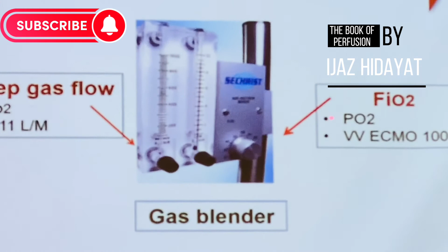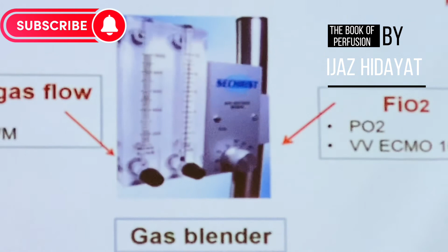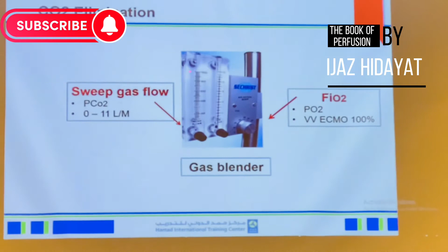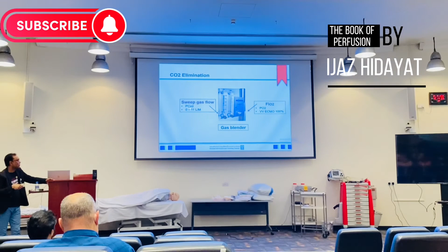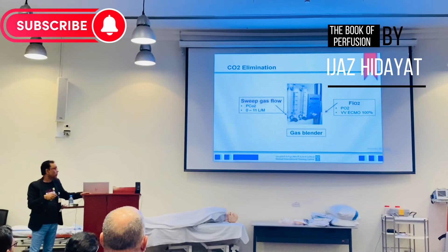So how do we eliminate the CO2? With the help of the gas mixture, we have two compartments. The first compartment is for the FiO2, fraction of inspired oxygen, where we increase the percentage, like 10, 20, 30, 40, 50% normally. But for ECMO, it is always 100%. With the help of the sweep gas, we remove the CO2, and the limit of the sweep gas is 0 to 11 liters per minute. So, for example, if your PCO2 is higher, you can increase your sweep gas to reduce it.